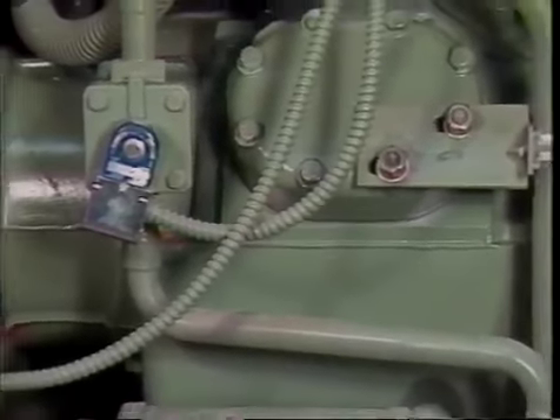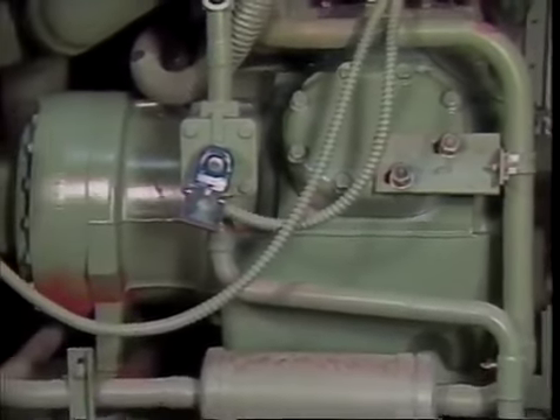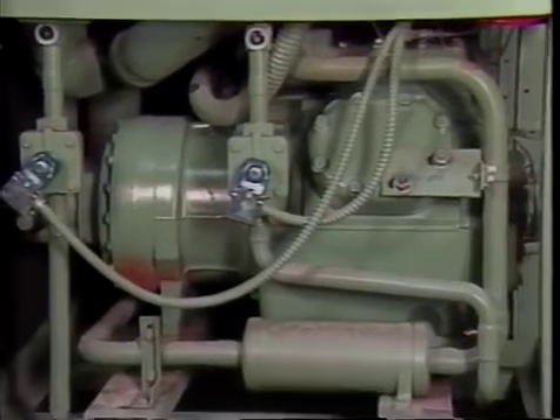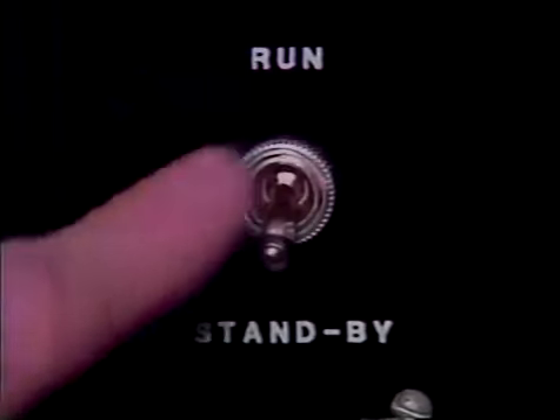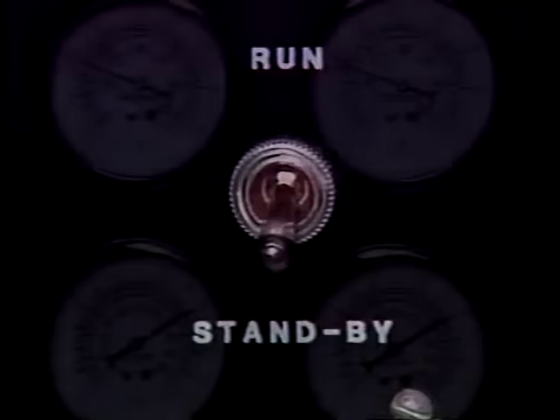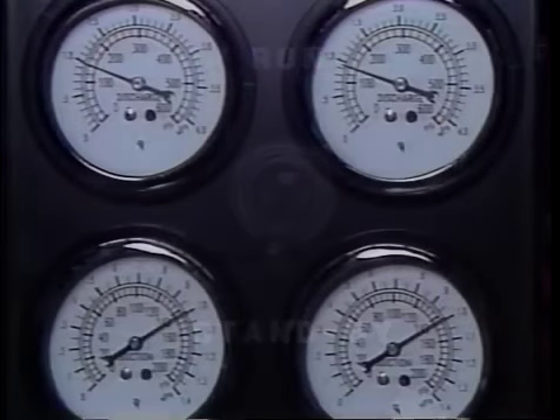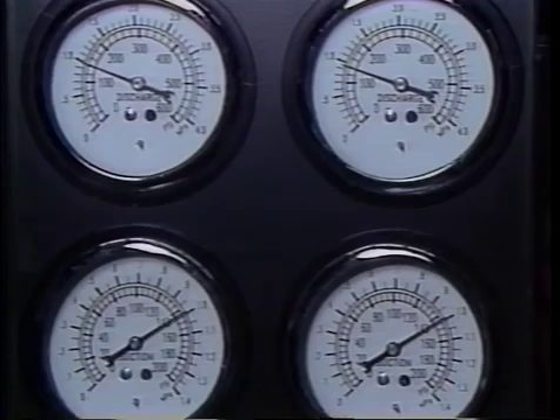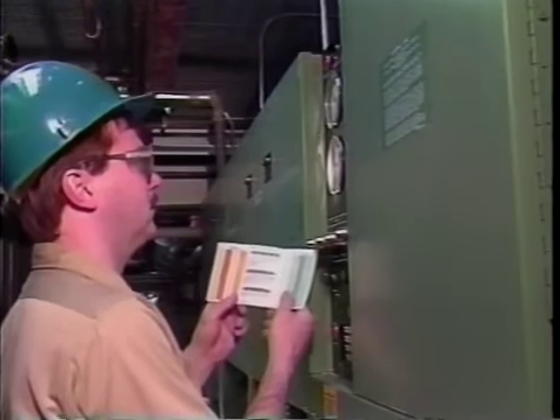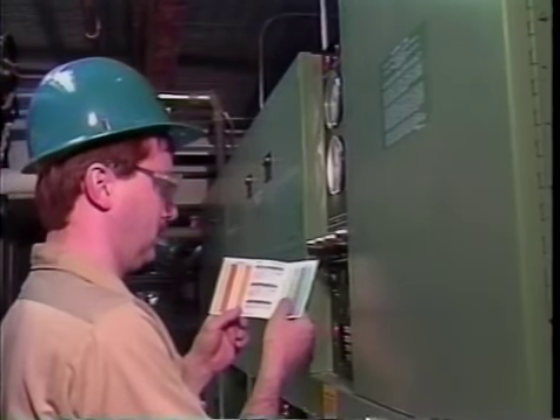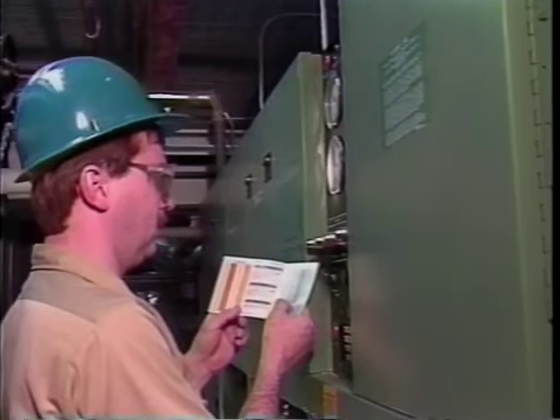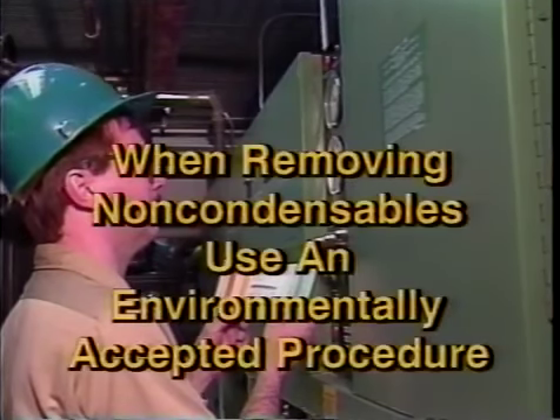It may not be possible to obtain the saturated condenser liquid temperature when the chiller is operating. If that's the case and you want to verify the presence of non-condensables, shut the chiller down and allow sufficient time for the pressures and temperatures to equalize to ambient conditions. You can then assume the condenser saturated liquid temperature to be at ambient temperature. Use the pressure-temperature relationship previously discussed to determine whether or not non-condensables are in the system. To remove the non-condensables from the condenser, use an environmentally accepted procedure.